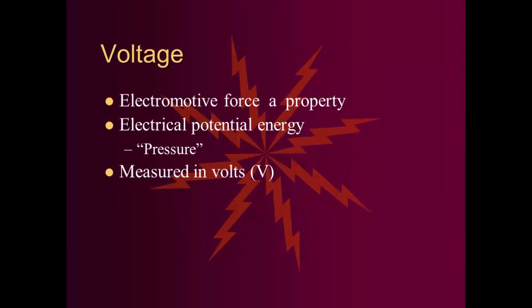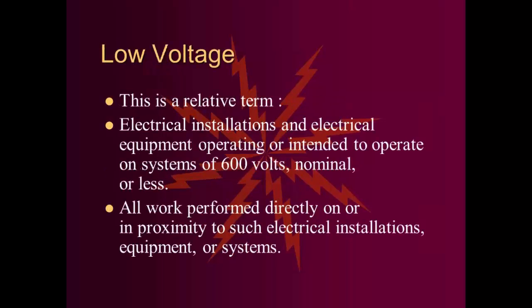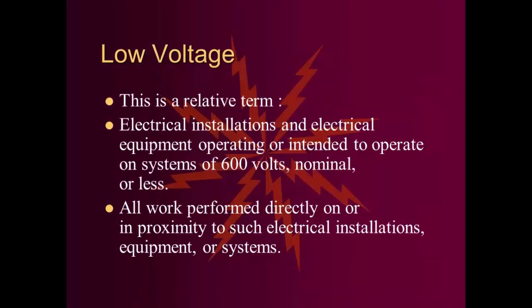Voltage is a property measured in volts. Low voltage is a relative term. Electrical installations and equipment operating at 600 volts nominal or less are usually considered low voltage. However, those of us on the 480 volt side would consider that high voltage. On the utility side, they'd call it low voltage because it's under 1,000 volts.